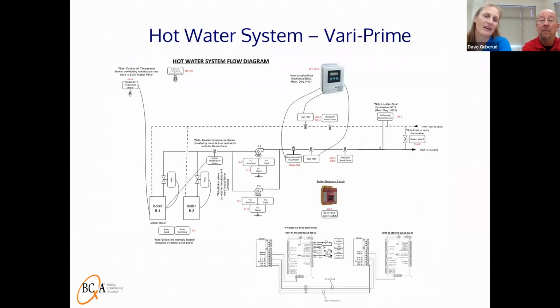So here we've got 2 boilers. We've got a variable primary system. So we've got our 2 pumps in parallel again with a DP sensor out there in the system. What we really liked about this graphic, we smiled because the control contractor, even though they weren't providing that equipment, they were responsible for wiring it. So they actually showed it and made it a part of their schematic. So we thought that was a smart and a good ad for the control contractor looking out for the client.